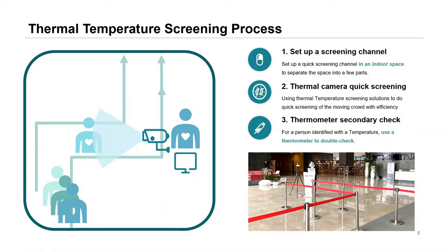For a person identified with a temperature, we recommend using a medical thermometer to confirm the elevated reading is genuine. The accuracy of our cameras is plus or minus 0.5 degrees, which can be improved to plus or minus 0.3 degrees with the introduction of a blackbody calibrator. A medical thermometer's accuracy is plus or minus 0.1 to 0.2 degrees, but it measures body temperature whereas our device measures skin surface temperature.